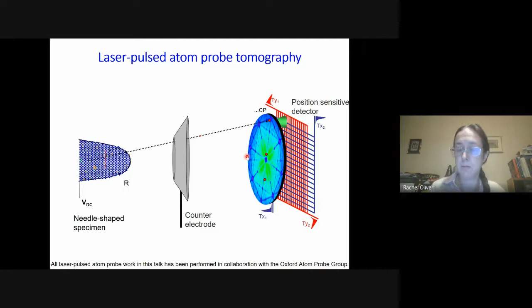So instead, we hold the sample at close to the threshold for field evaporation, and then we pulse a laser, which just warms it up a tiny bit, and that lowers the threshold of field evaporation, causes the ions to evaporate. And then we use the same type of analysis. We work out their X and Y and Z position from their arrival position on the detector and the order at which they arrive. And we use their time of flight to work out their atomic species.